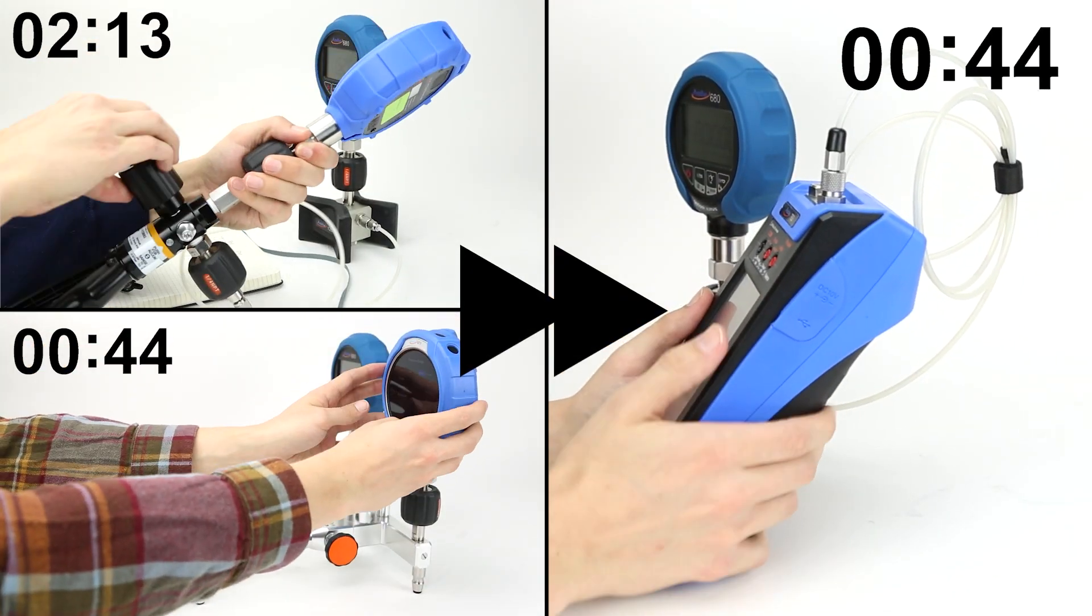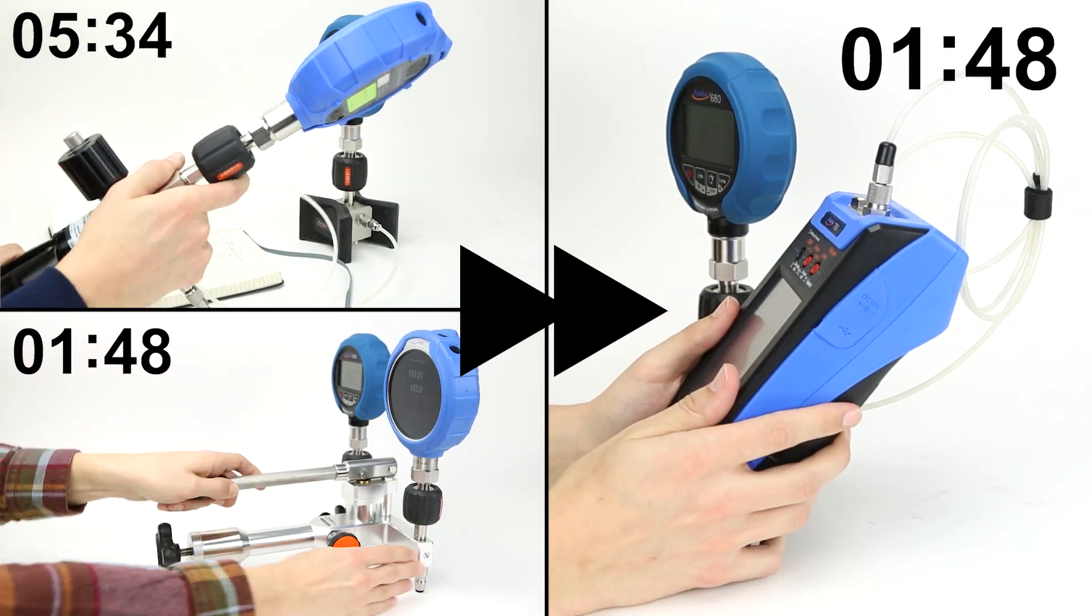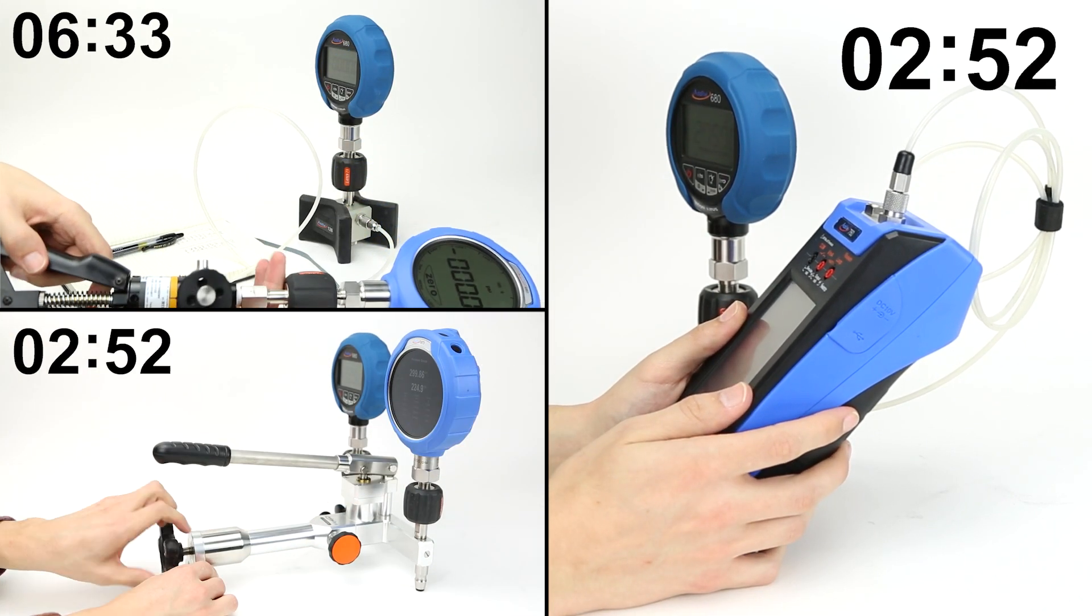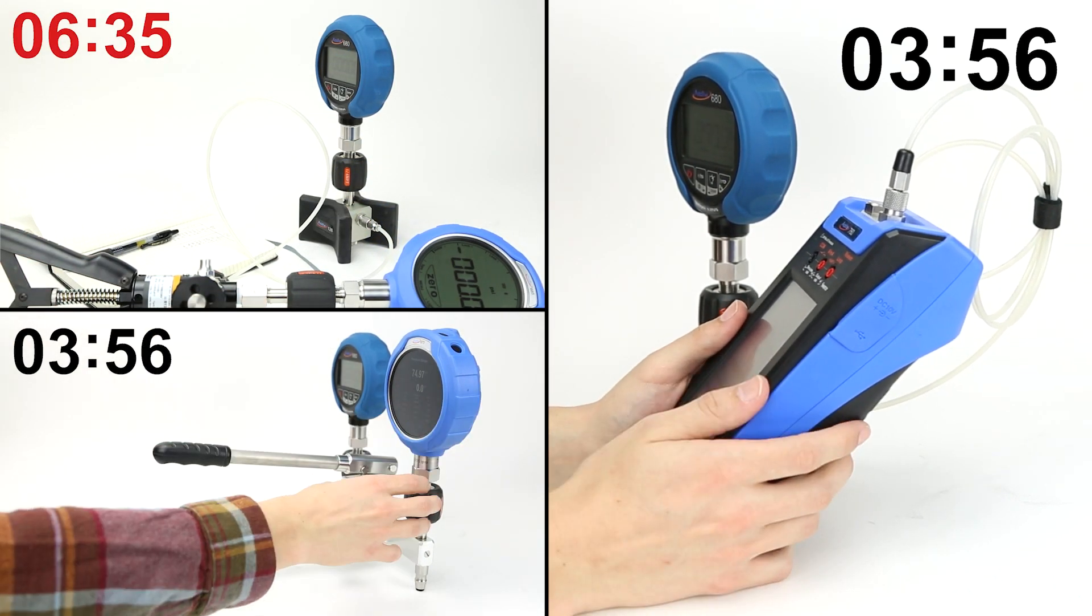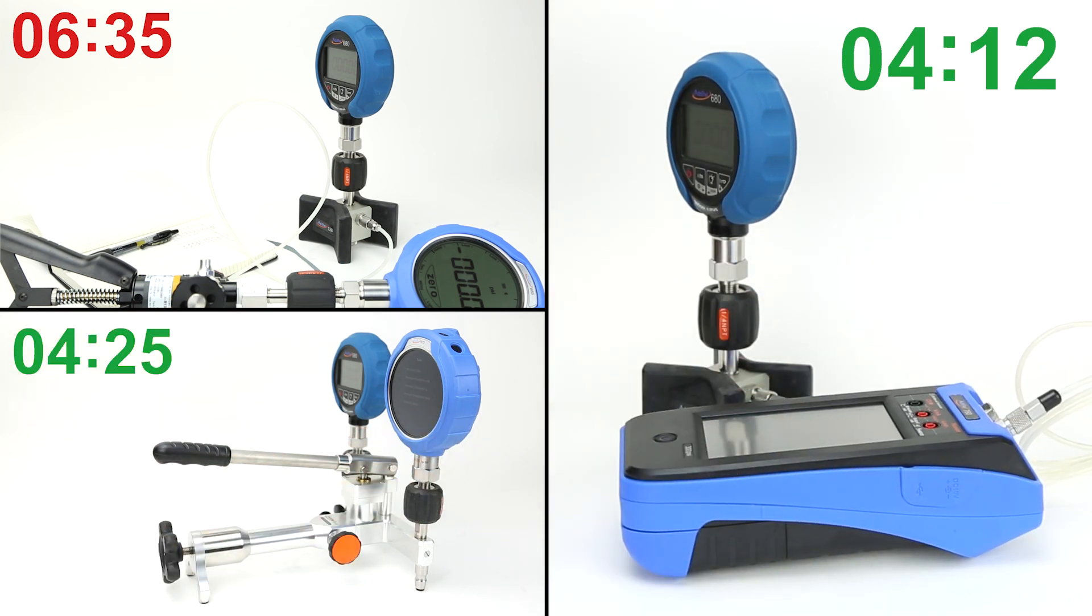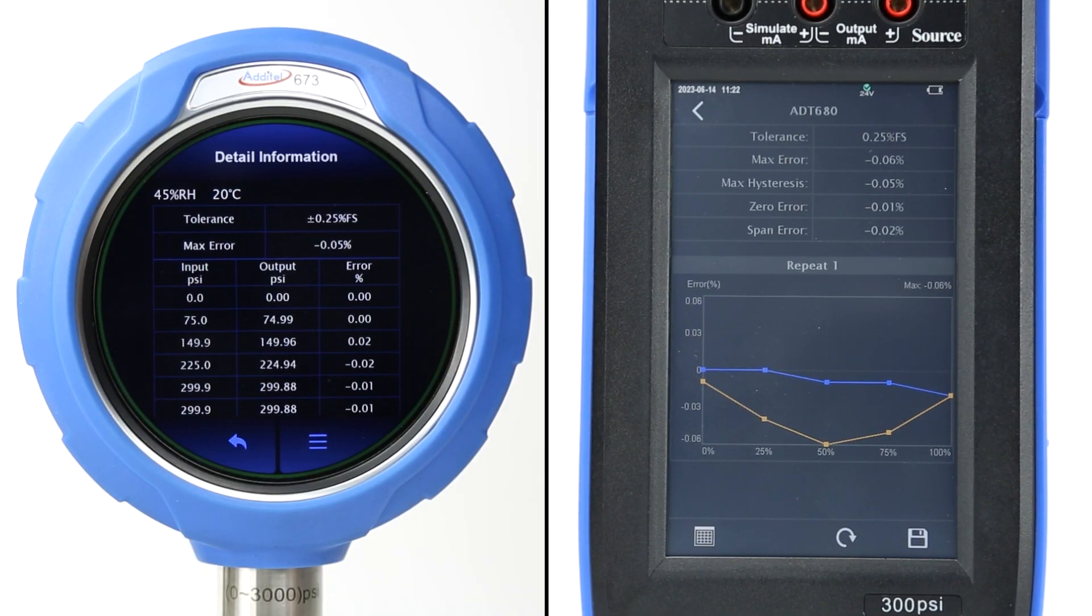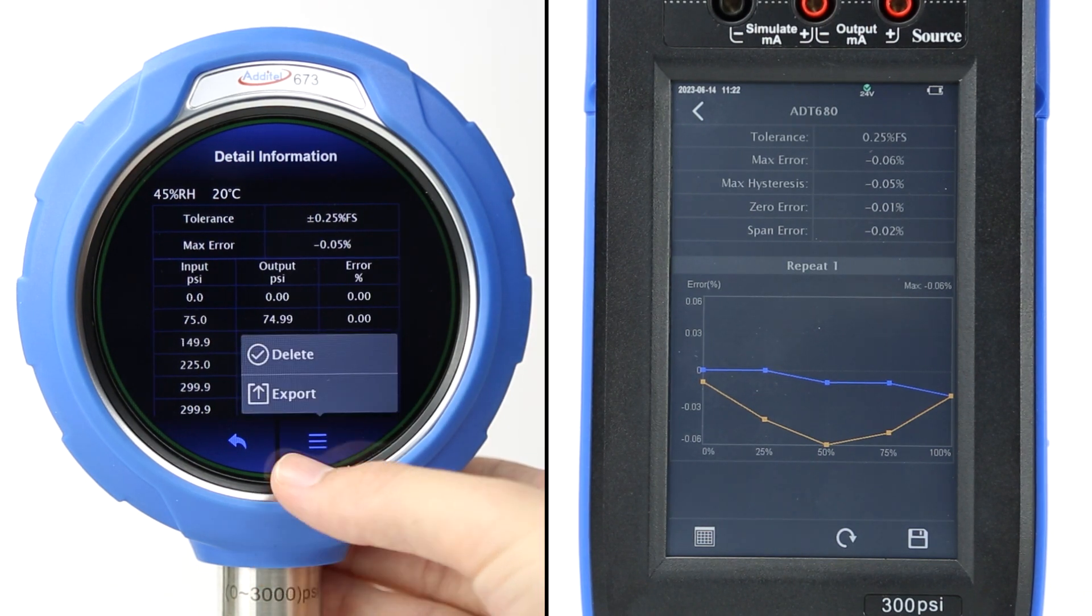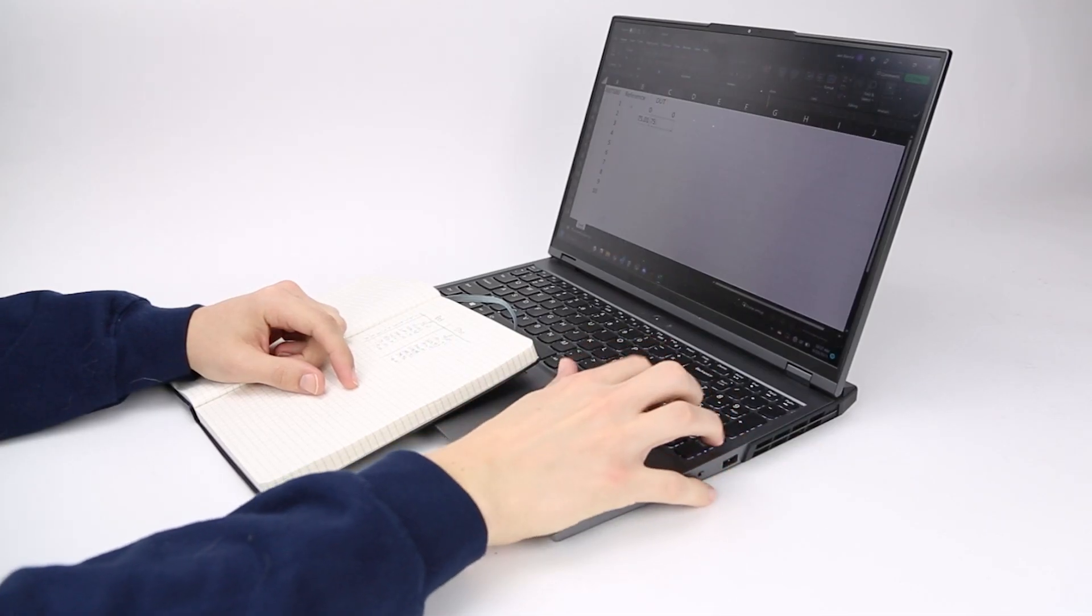If we fast forward the testing procedures, we can see that for a 9-point round trip test, Technician 1 took over 6 and a half minutes, while Technicians 2 and 3 only took 4 and a half minutes, from setup to finish. Technicians 2 and 3 also have their calibration data ready to view or export immediately, while Technician 1 still has to enter all of their data manually into their lab software.